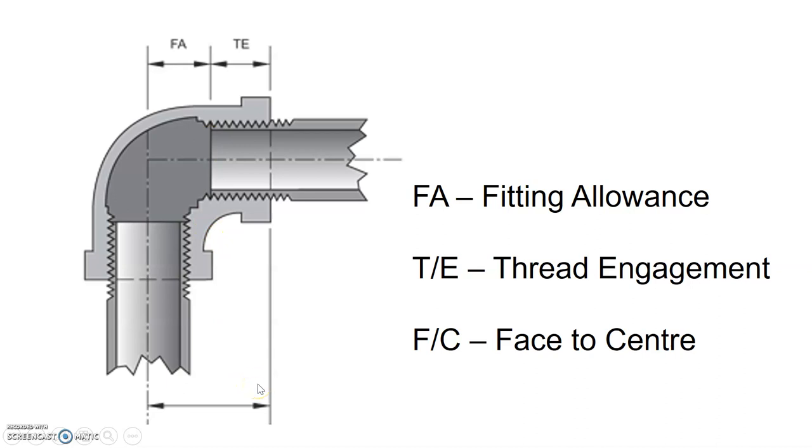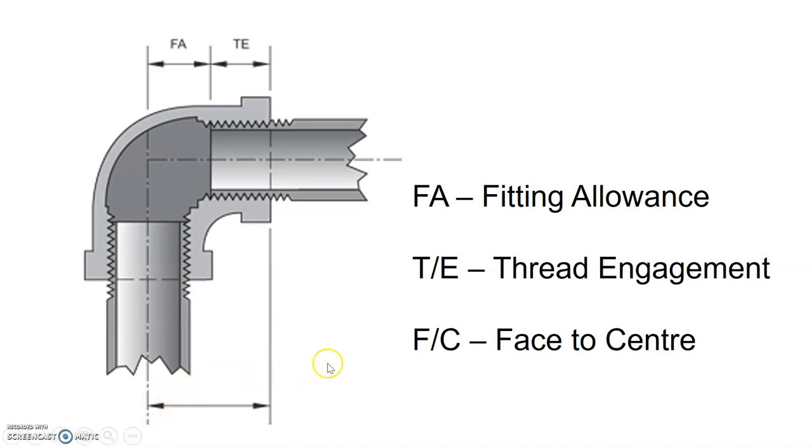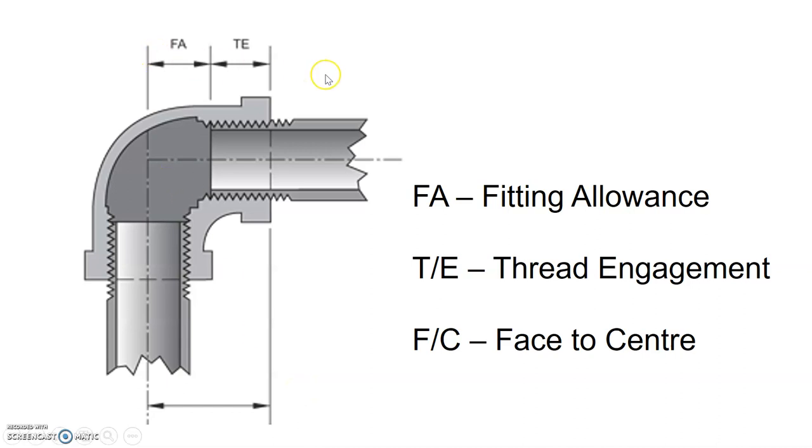Lastly, the face to center measurement, or the F/C, is known as the measurement from that same face where the pipe enters all the way over to the centerline on the other side where the FA ends. That is known as the face to center measure. If you have noticed on the picture, the F/C distance at the bottom includes the TE and the FA at the top. That means that there are three pieces to the pie, as they would say, and all we need is two pieces to find the third piece.